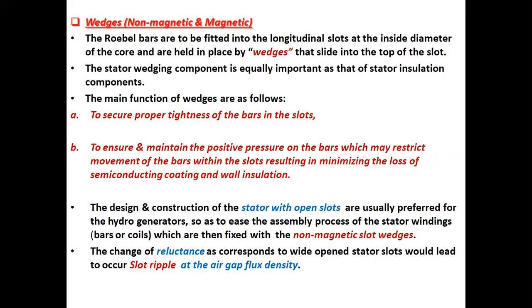The design and construction of the stator with open slots are usually preferred for the hydro generators so as to ease the assembly process of the stator windings, that is bars or coils, which are then fixed with the non-magnetic slot wedges. The change of reluctance corresponding to wide open stator slots would lead to slot ripple at the air gap flux density.